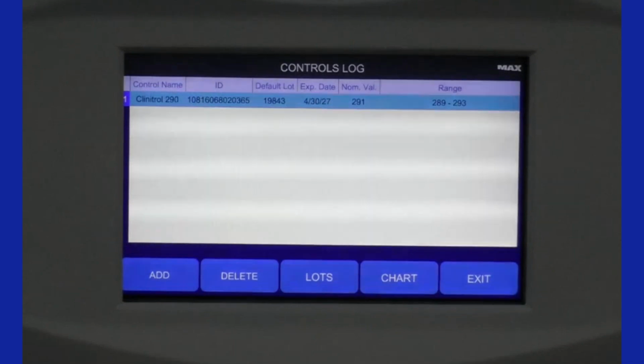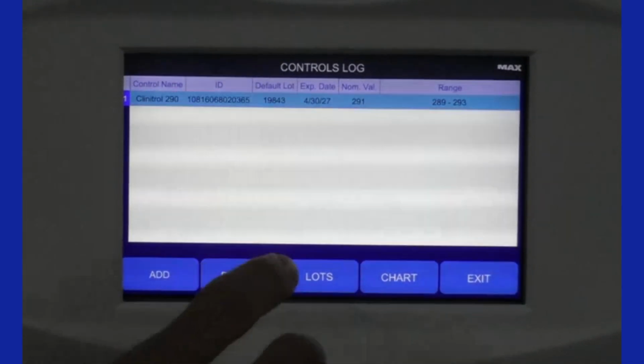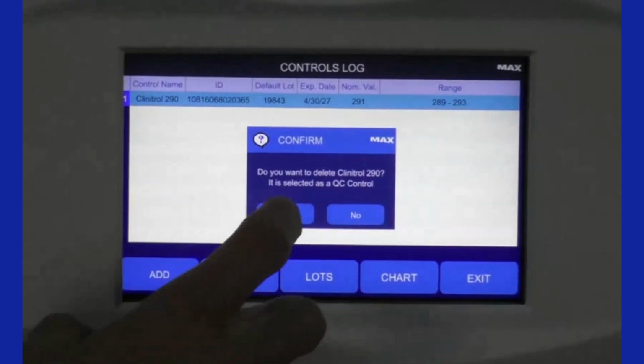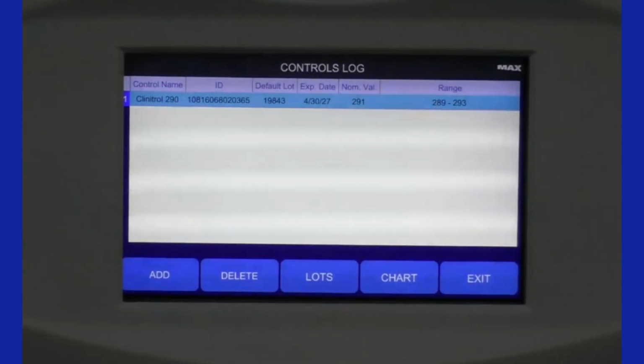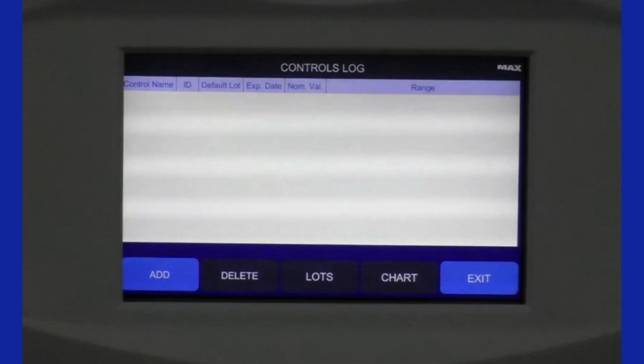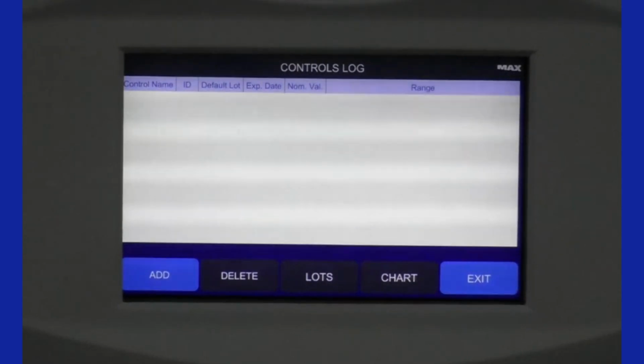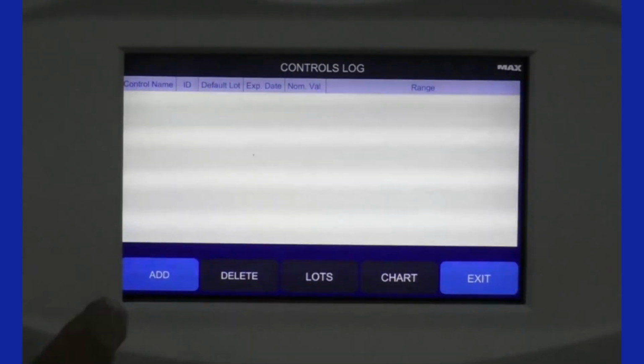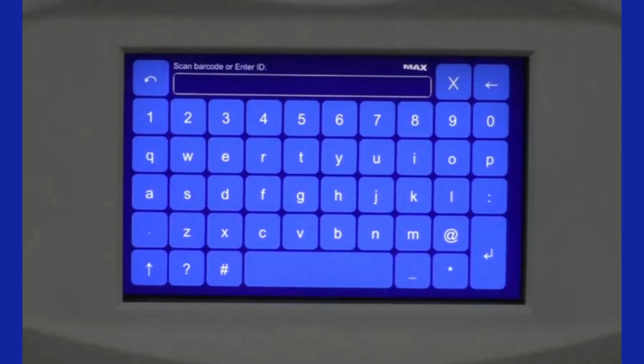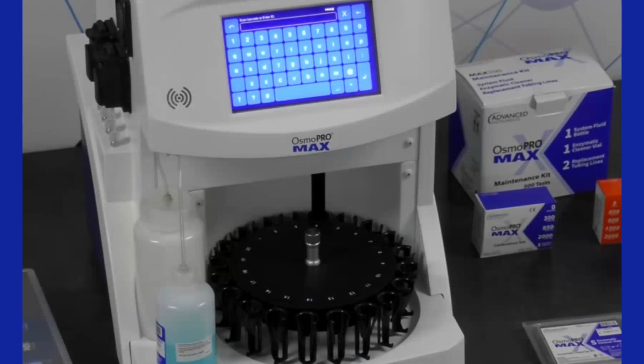What I can do is just have it selected, which I already do. Just hit this delete button. It's going to make sure that I want to do that. I'm going to say yes, because I want to show you how easy it is just to log another control into the system. So to put another one in here, you'll say add. And then it's asking me to scan the barcode or enter the ID. So let's say if you're using a third-party control, this is where you would manually input that information. But when you're using Clinitrol 290 that's provided by Advanced Instruments, you have the option to just scan in.